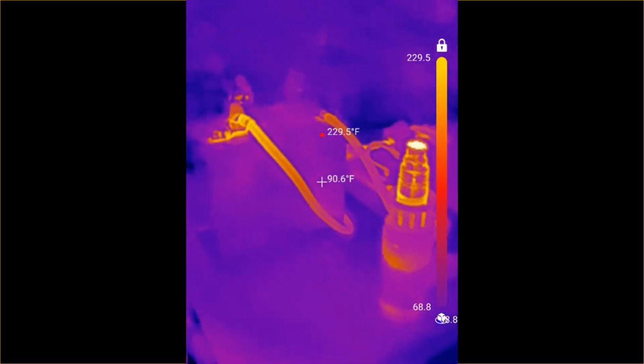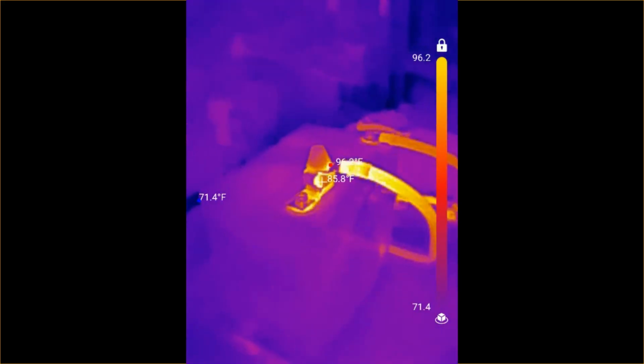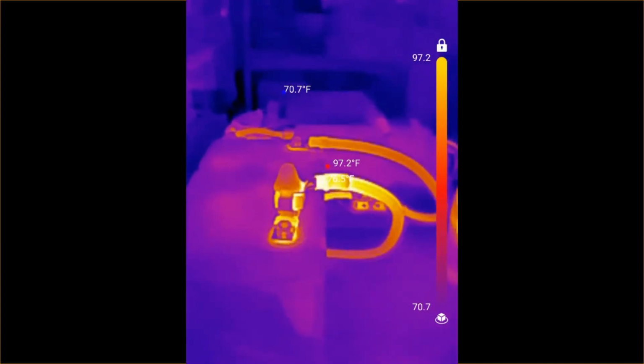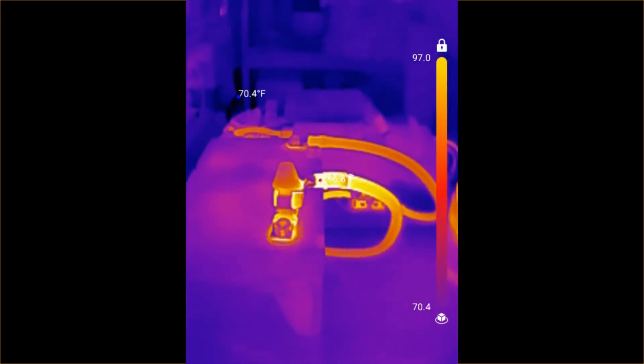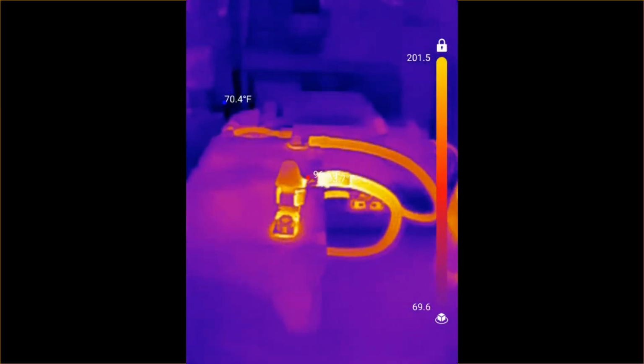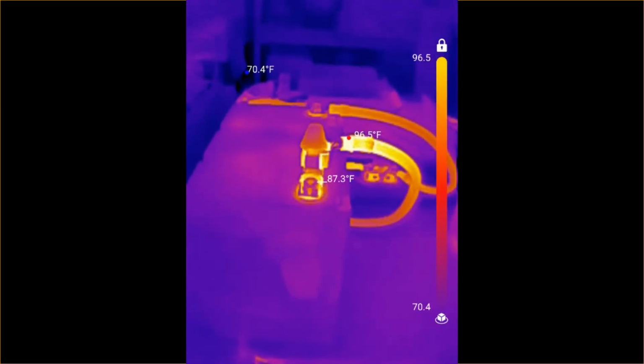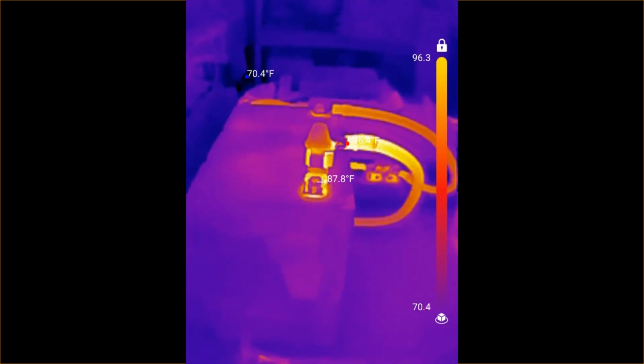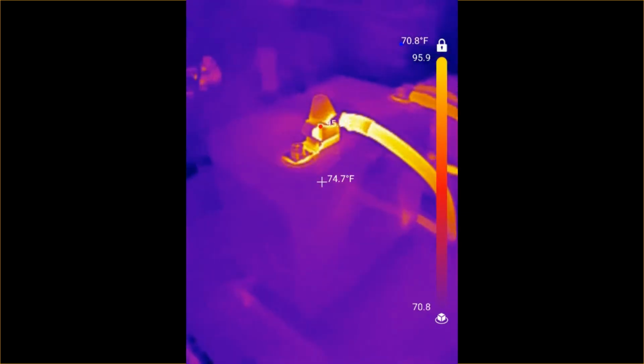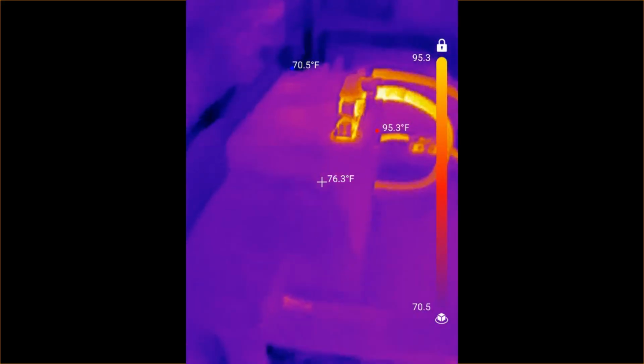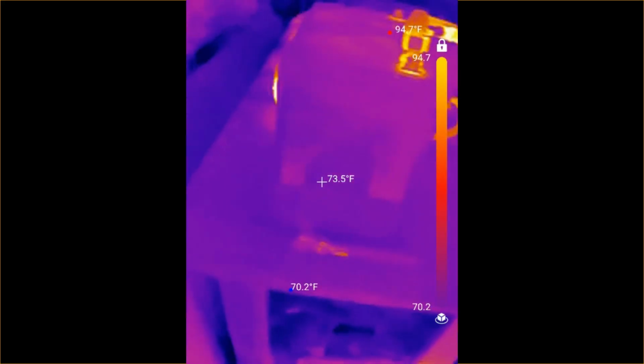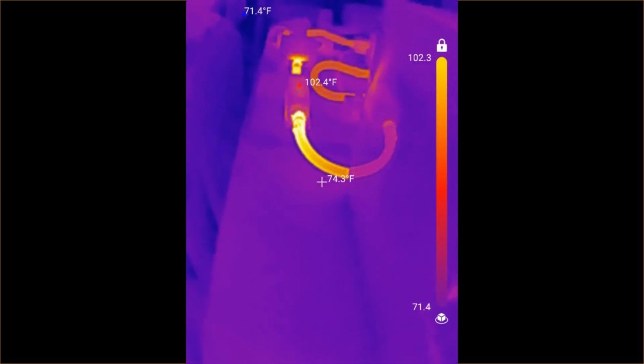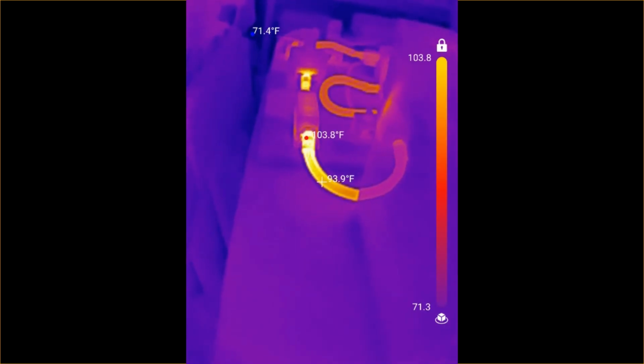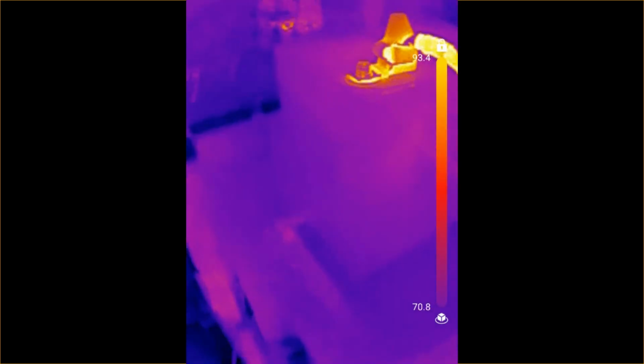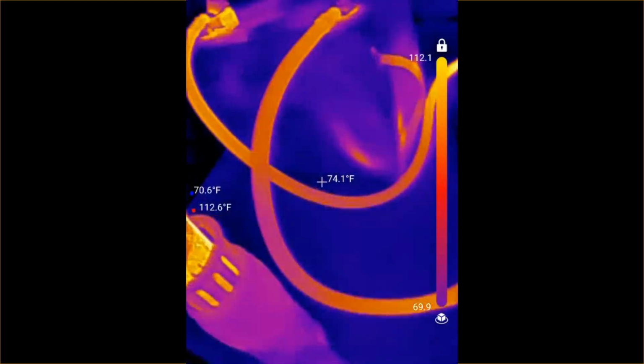Okay, the wire right here on the battery got to 97 degrees, which isn't too bad. Let's see, that's 87, 89 degrees right on the fuse. I don't see any buildup really. So the battery cable is getting about as hot as anything. There's a little bit of buildup here, let's see what that is.